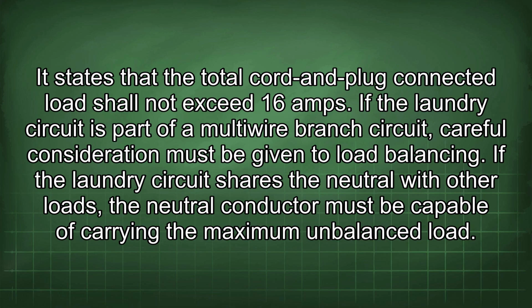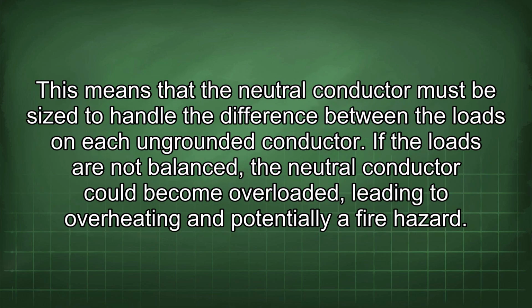If the laundry circuit is part of a multiwire branch circuit, careful consideration must be given to load balancing. If the laundry circuit shares the neutral with other loads, the neutral conductor must be capable of carrying the maximum unbalanced load. This means that the neutral conductor must be sized to handle the difference between the loads on each ungrounded conductor. If the loads are not balanced, the neutral conductor could become overloaded, leading to overheating and potentially a fire hazard.